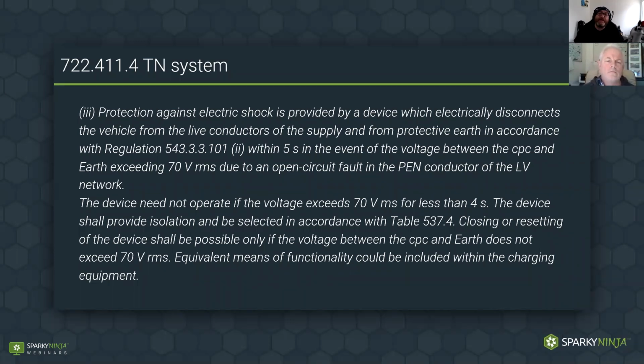And it must do this within 5 seconds in the event of a voltage on the CPC going to 70 volts. And it has to happen in a period of time, not less than 4 and no more than 5 seconds. So in the life of the 18th edition, some devices came out that tried to achieve this. We used to call it a unicorn device, then some manufacturers brought out devices that achieved this, but now with the 18th edition Amendment 1, they've added guidance.